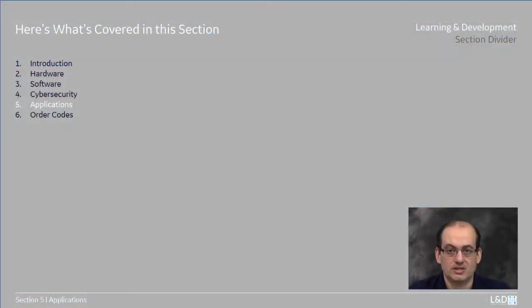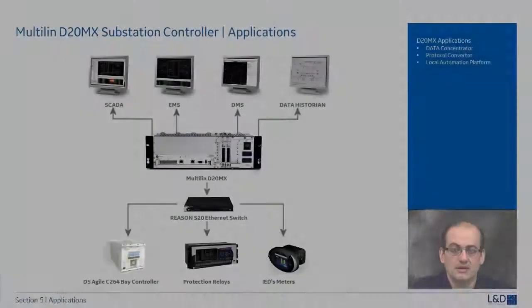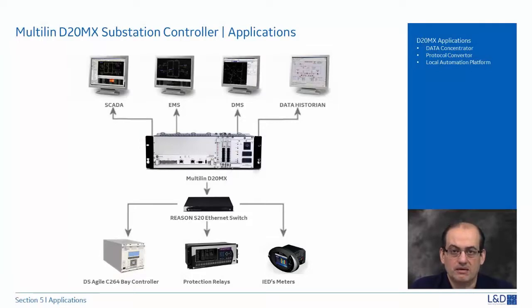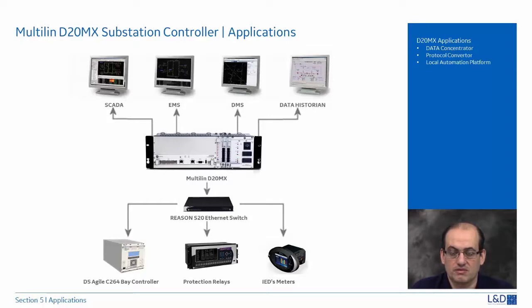In this section we'll discuss the applications of the D20MX in substation automation. One of the main applications is as a data concentrator, collecting, filtering, and reordering information before sending it to an EMS, DMS, or any SCADA master. It also has the ability to do protocol conversion — so while downstream devices may be talking Modbus, L&G, DNP, or other legacy protocols, and the SCADA master uses only one protocol like IEC 101 or DNP, the D20MX acts as a protocol converter between downstream and upstream.